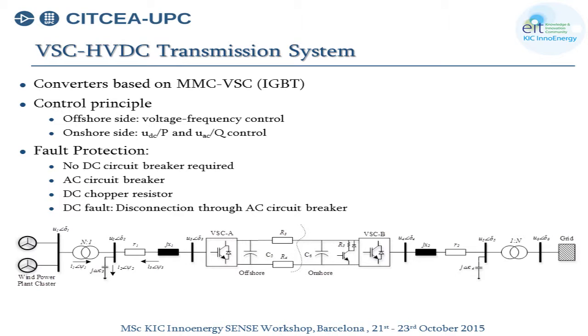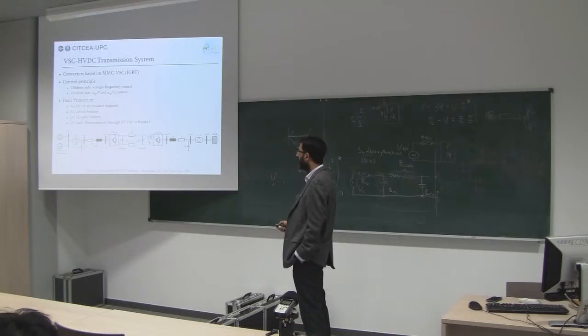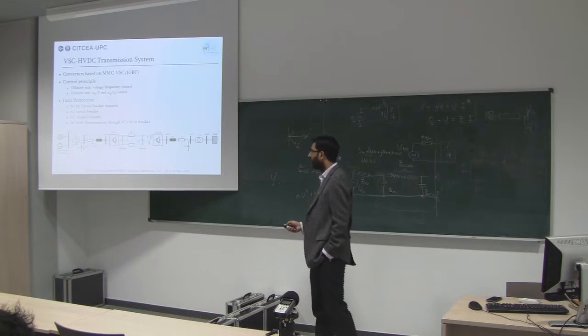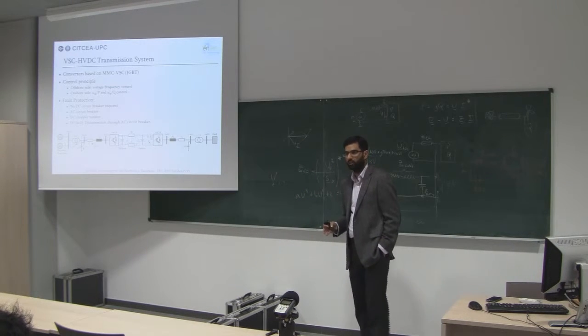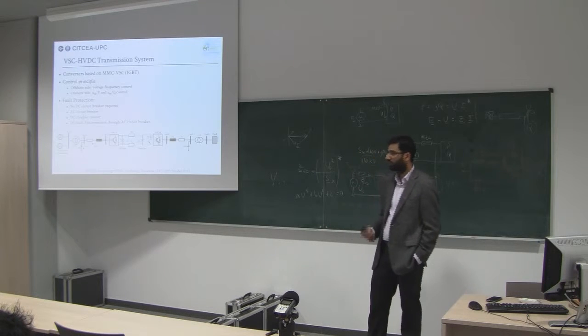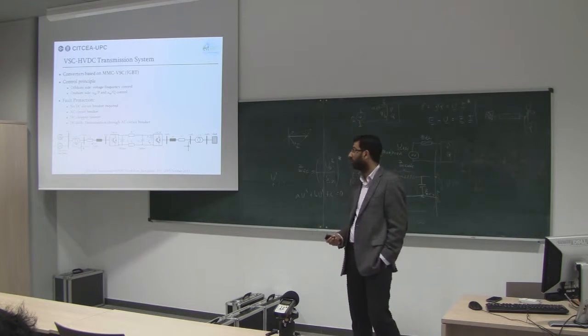In this setup we have two different operational modes. The grid-side converter works in grid synchronous mode, where the main frequency is provided by the grid, not the converter, and it operates in power control mode. On the offshore side, the converter has to provide the main frequency to the network, and all the wind turbines must synchronize with this frequency.